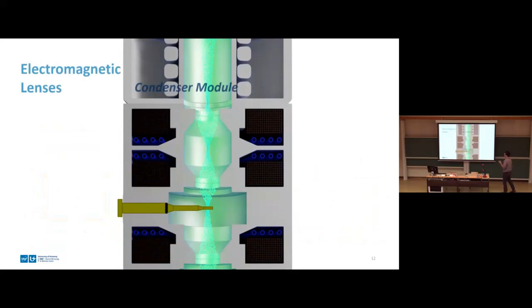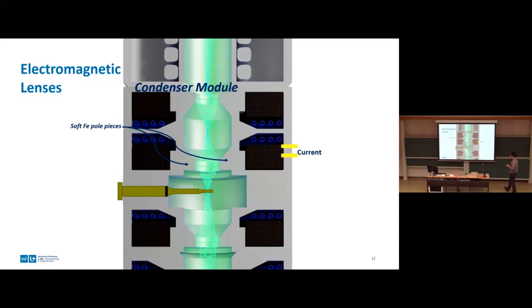But once we get our electrons, we'll take them into the microscope. The first module that we'll find is a condenser module. In the condenser module, you find your first electromagnetic lenses of the microscope. How do these work? By running a current around wires surrounding the aperture, we'll magnetize soft iron pole pieces. And this magnetic field, due to Lorentz force, will create a spiraling effect on a charged particle traveling through it, in this case an electron, and it will focus it. Very analogous to what you find in glasses for vision. And by changing this current in the lens, we can change the focal length. And that's important. Here we are shaping the propagation of electrons along the column.